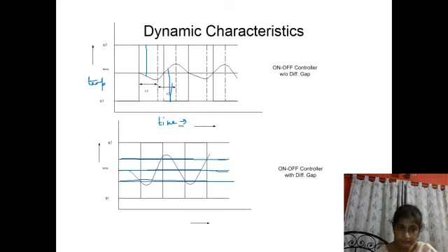This is the process dynamic characteristics, and the controller switching will operate at the point of crossing of the set value. When it goes below the set value, the controller will turn on. When it goes above the set value, it will turn off. And this is without the differential gap. For the differential gap, instead of operating at the set point, there is a differential delay. This is the upper set value, and this is the lower set value. So instead of operating at the set value like the case without differential gap, the controller will turn on when it goes below the lower set value, and it will turn off when it goes above the upper set value. So the time delay is more than in the previous case.